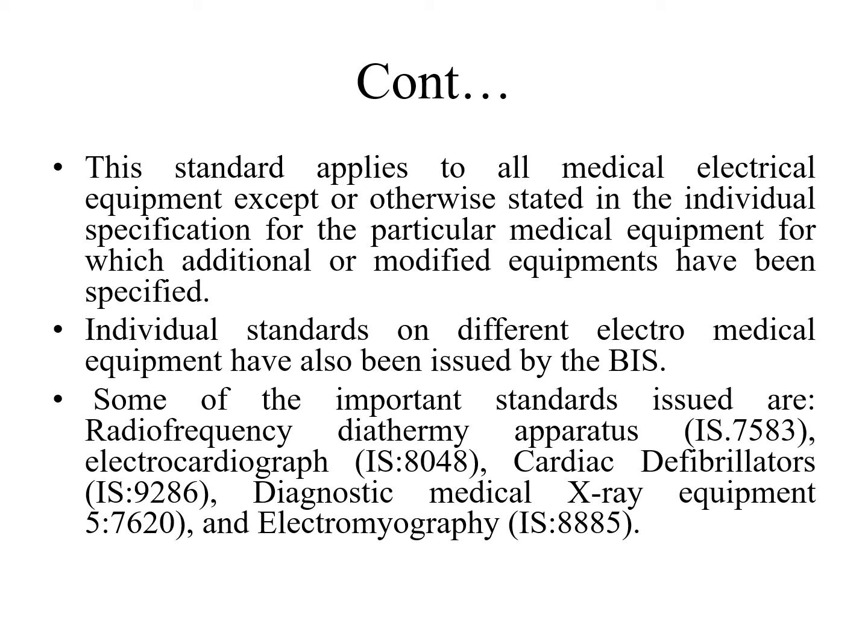Individual standards on different electro-medical equipment have also been issued by the BIS. Some of the important standards issued are: radio-frequency diathermy apparatus specification IS 7583, electrocardiograph IS 8048, cardiac defibrillator IS 9286, and diagnostic medical X-ray equipment and electromyography.